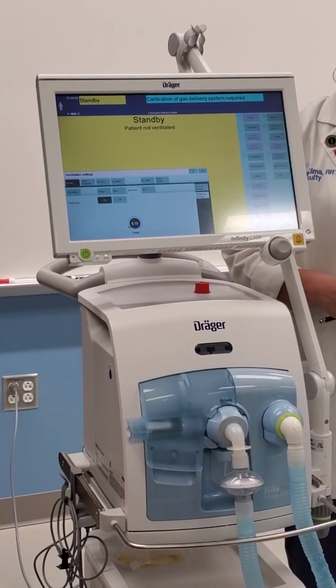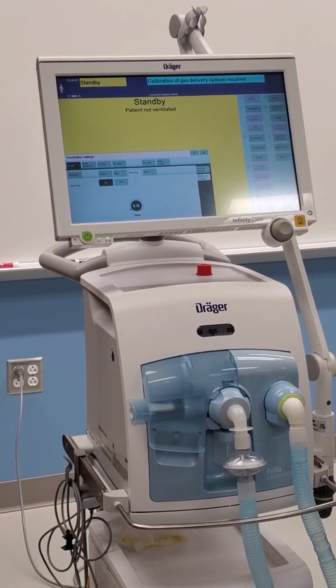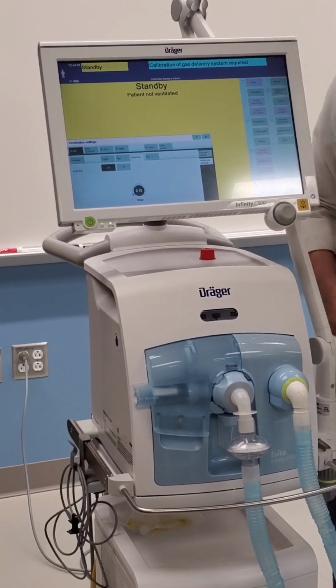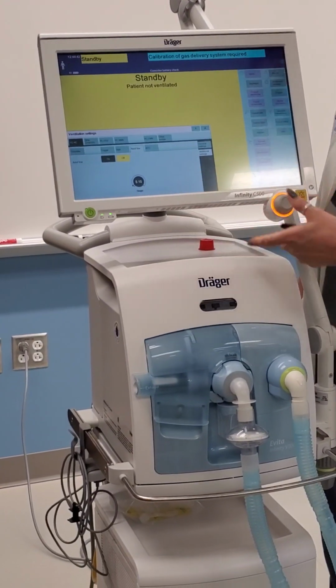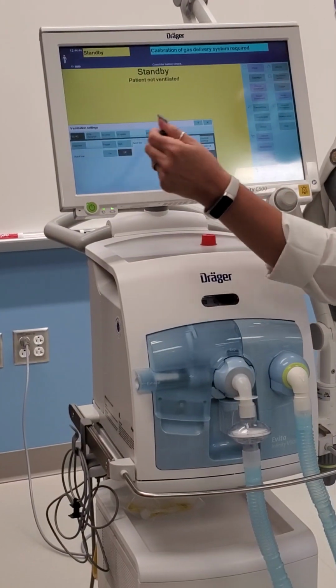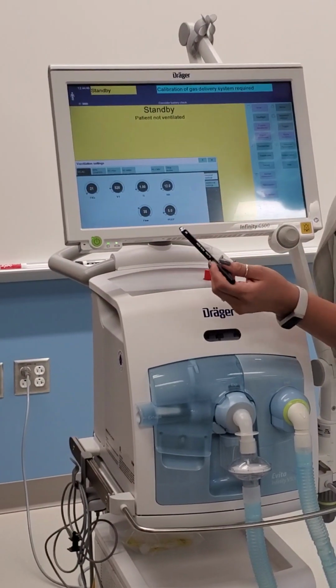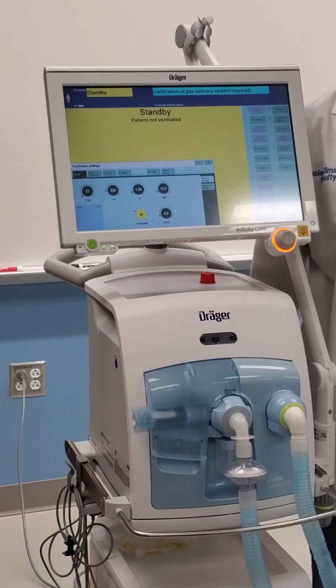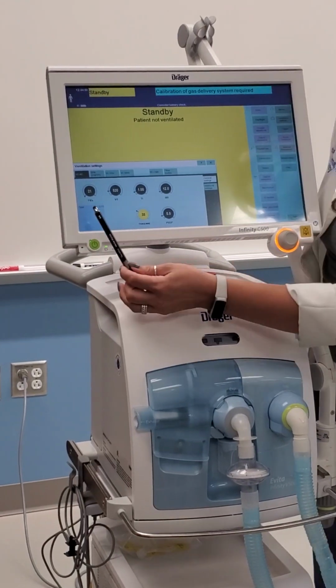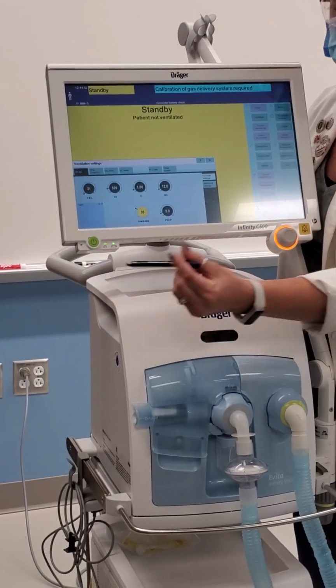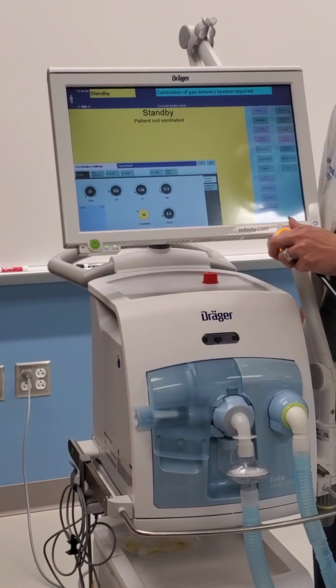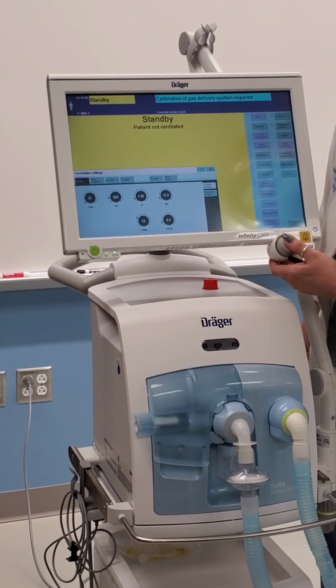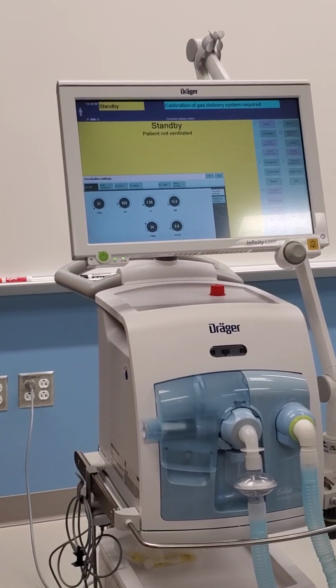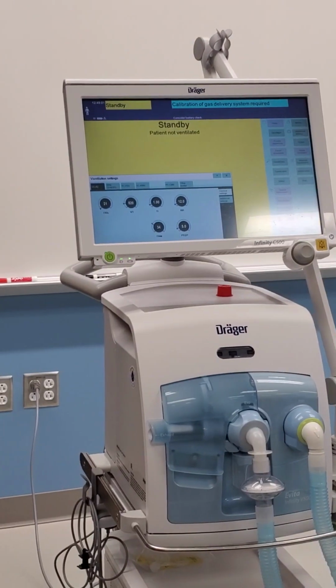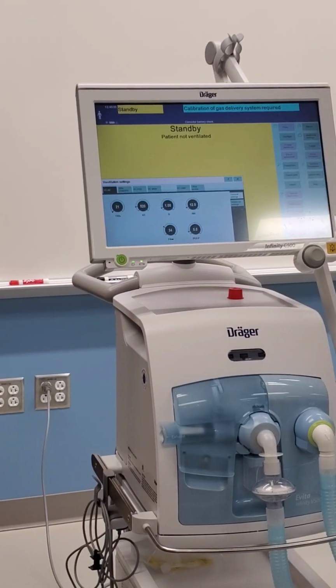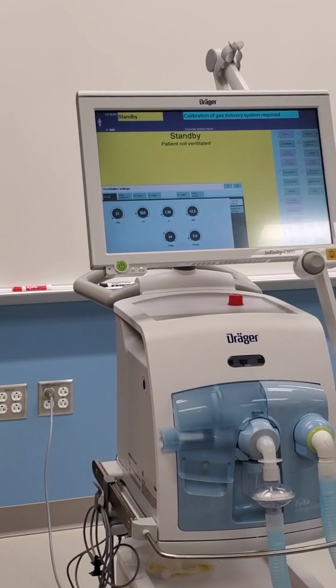It's a little bit more comfortable for the patient because of that variable flow. You can turn it off, and I'm going to show you what happens to your main settings. If you go back to general settings, see how there's now a flow rate? But over here it says T-plat, and you have to turn up your flow until that's as close as it can get to 0, which is 34. Kind of low, right? That may not be enough for your patient.